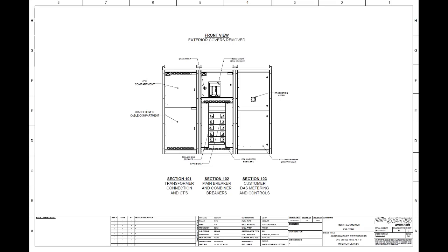And then on one side of the compartment is going to be a production meter that the customer had requested we provide on this with PTs, CTs. We have an auxiliary transformer cabinet where we would have some control power, station power, distribution panels to power up the meter, power up the circuit breaker, and then utility metering and a customer metering compartment for installation of any of their components as well.